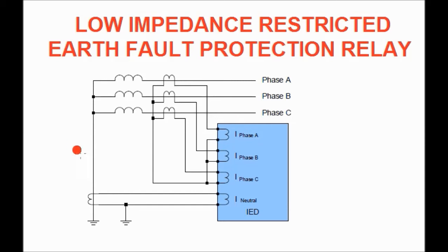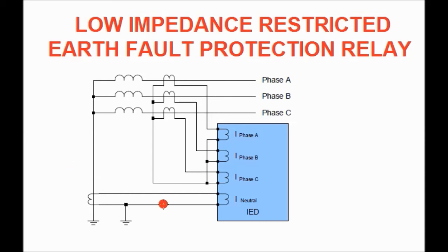The connection is very simple — no high impedance is required and no varistor is needed. The main advantage of the low impedance type restricted earth fault relay is that the connection diagram is very simple, no varistor is required, and there is no calculation needed for resistance values.